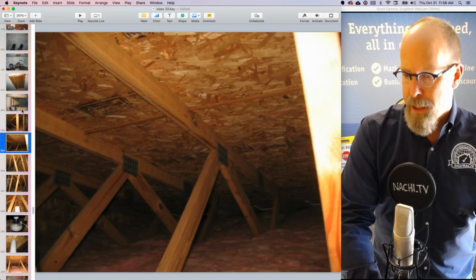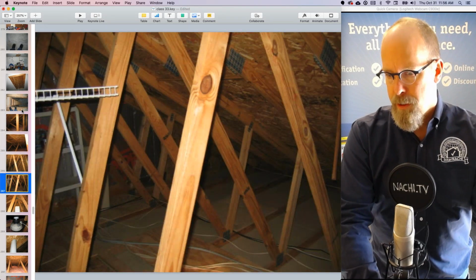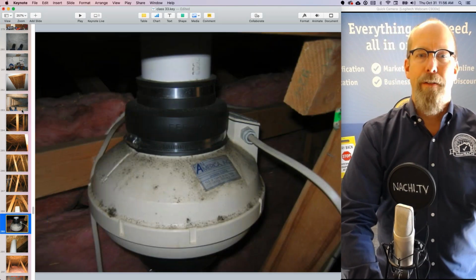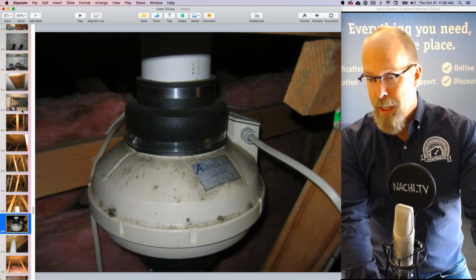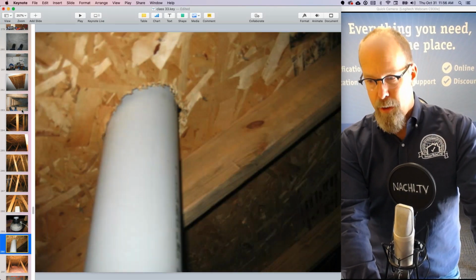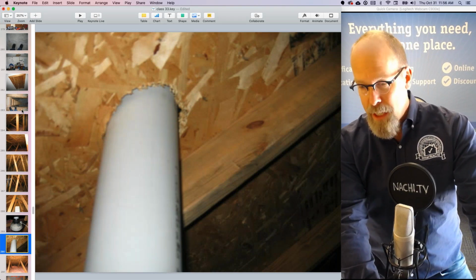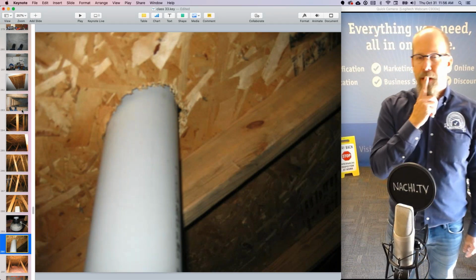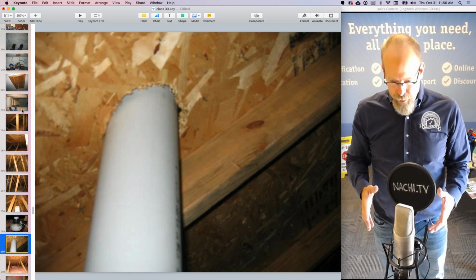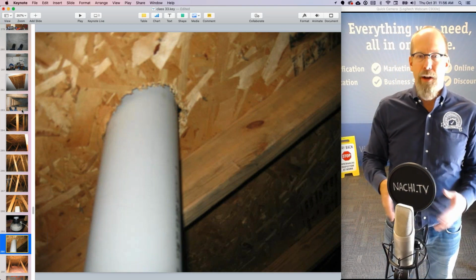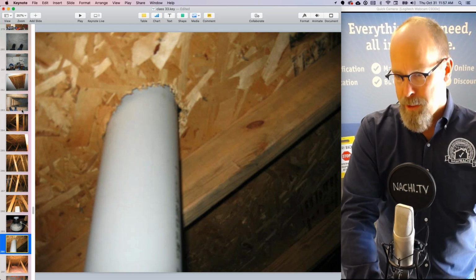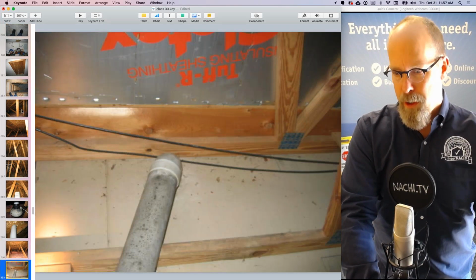And here's the attic above the garage. Wiring and all that stuff, and up there's the radon fan. So we can take a look at that and see if it's compliant with modern standards for a radon mitigation system. And that's why the flashing on the roof was so damaged, remember, because it was different from all the rest. It was a cheap rubber thing that the radon mitigation system folks installed. I used to install radon mitigation systems, so I know a little bit about inspecting them.